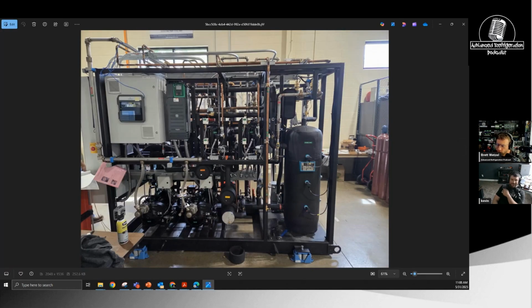Hey, what are these? Those Vibrasorb clamps. No, those are reliefs. That's their way of enclosing the reliefs, because from Copeland they just come out the front. If they go off in a room, certain municipalities in Canada don't allow that, so they have to be encapsulated. So then all your reliefs go out together, probably through this header, up and out. Yeah, just those 2 reliefs, because they're right in front of your face. Every other relief is piped on the outside of the building, which I'm not a big fan of. I'd rather them be at the rack, because when we popped them, it took forever to get a ladder out there and get them shut off.